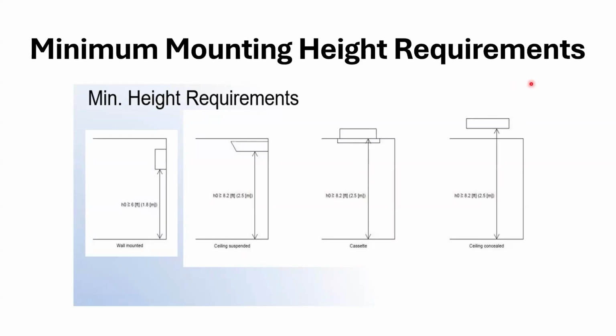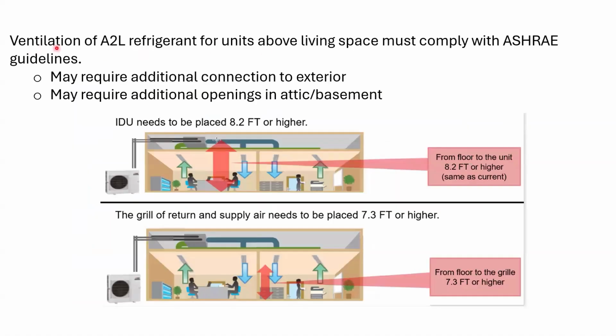So, ventilation. A2L refrigerant for units above the living space must comply with the ASHRAE guidelines. It may require additional connection to the exterior. It may require an additional opening in the attic or basement. So again, what they're showing right here is that the indoor unit needs to be placed 8.2 feet or higher.